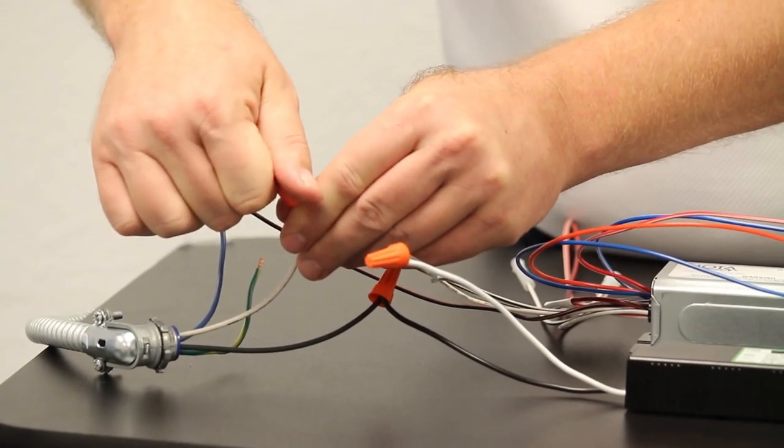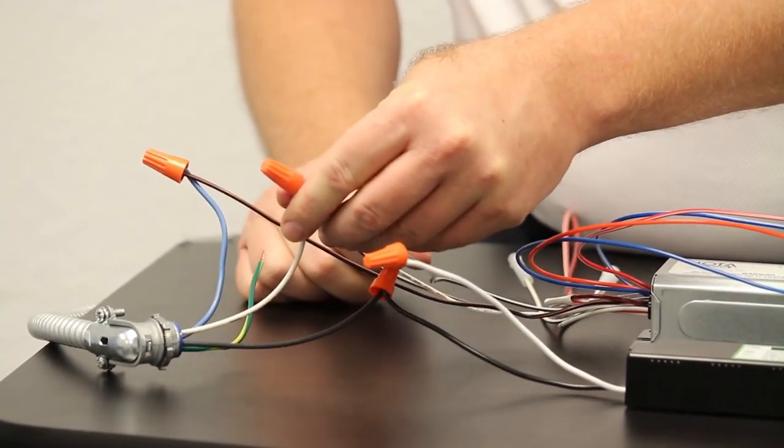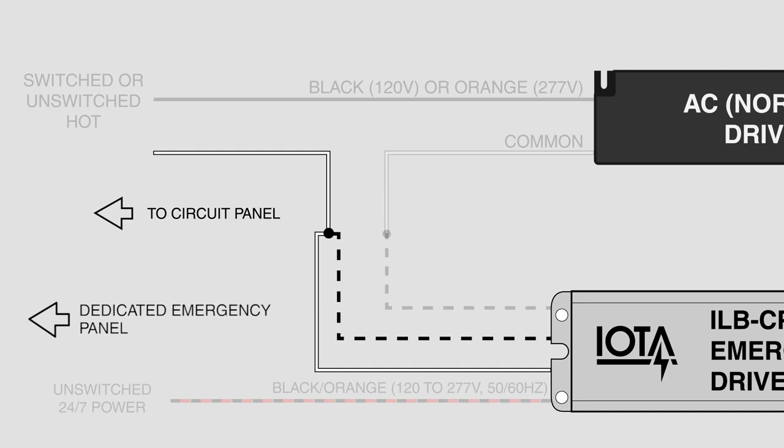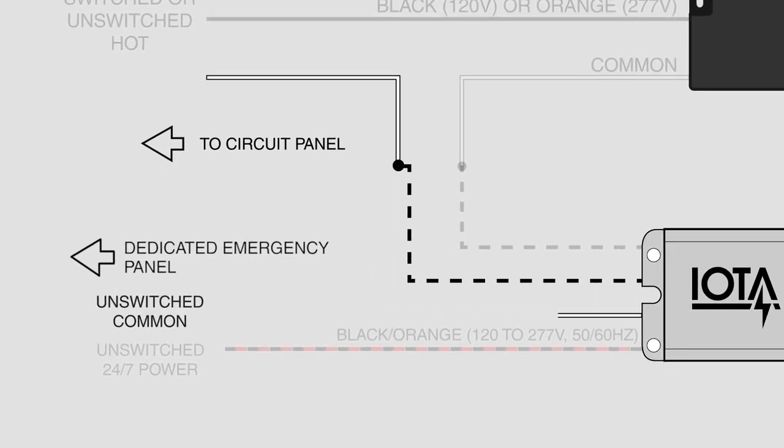If you have an electrical panel that you have run for a dedicated emergency operation, the white wire would go to that panel directly, instead of being connected at the same point that the white-black wire attaches for the normal driver.